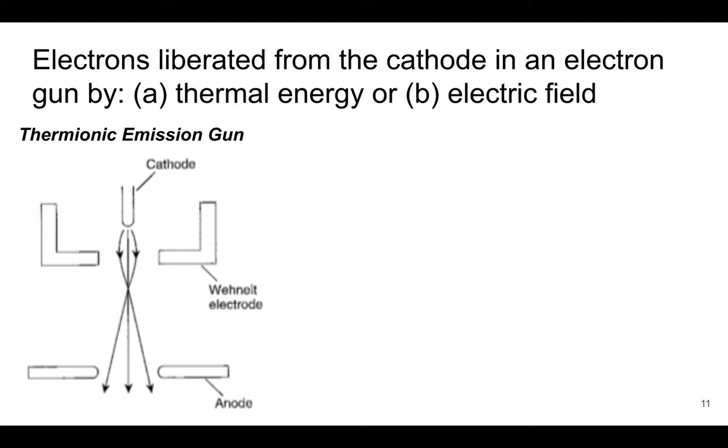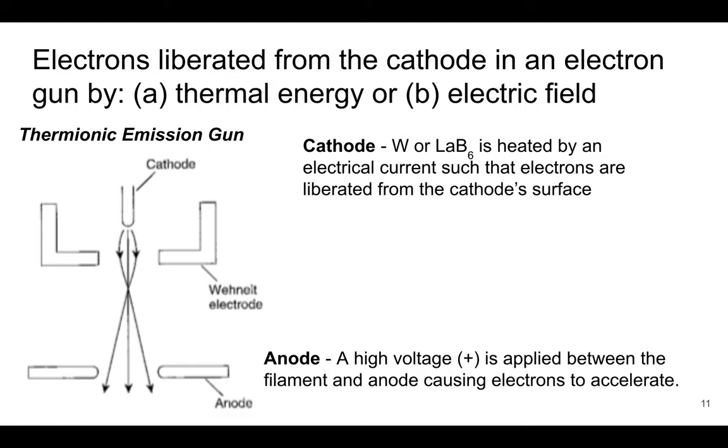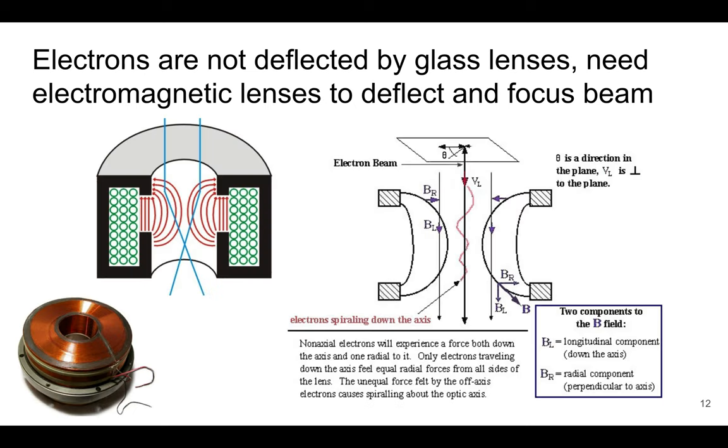So here, I just want to go through some of the components that we talked about for SEM. Again, very similar. So electron gun, the same types. We can have a thermionic gun, it could be tungsten or LaB6, that will affect the brightness and so forth. And we can also have the field emission guns, and that's what a lot of the new guns are going to.